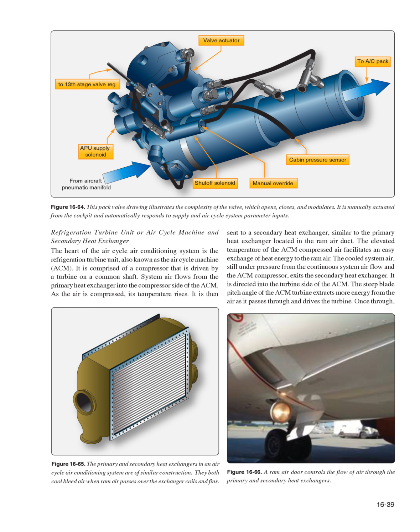It is then sent to a secondary heat exchanger, similar to the primary heat exchanger located in the ram air duct, where the bleed air is cooled when ram air passes over the exchanger coils and fins. The elevated temperature of the ACM compressed air facilitates an easy exchange of heat energy to the ram air. The cooled system air, still under pressure from the continuous system air flow and the ACM compressor, exits the secondary heat exchanger. It is directed into the turbine side of the ACM.